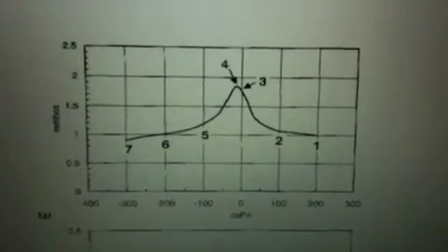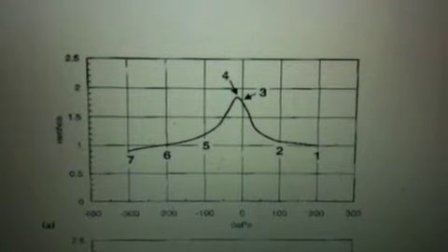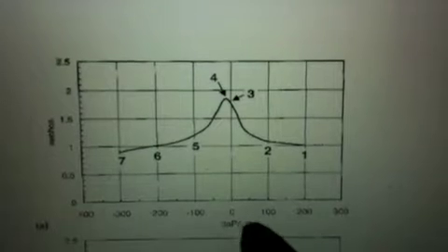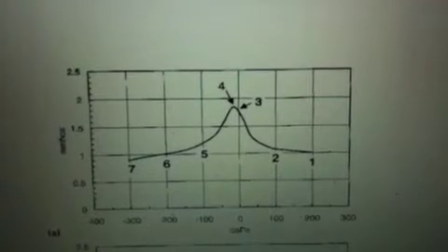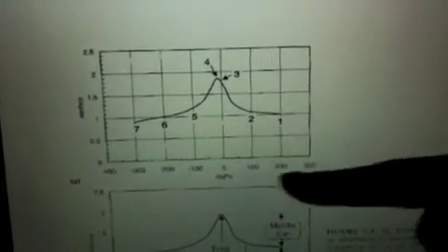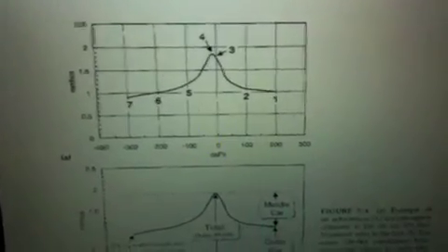On this slide, the top graph of the slide, I have a very basic tympanogram. What you should notice is that pressure is on the horizontal axis, so we go from negative pressures to 0 decapascals to positive pressures. And on the y-axis is the admittance of the system. You'll remember when we're doing tympanograms, we are sweeping pressure from positive to negative values. And what we are measuring is the immittance of the tympanic membrane in particular.